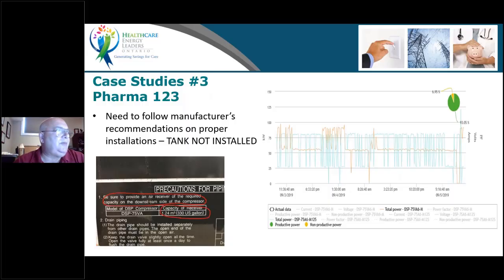This is the exact same customer. What I pointed out to the customer, after 10 years of him having the system in place, is that the name tag on the compressor itself specifically says, be sure to provide an air receiver of the required capacity downstream of the compressor. There was none. These compressors fed directly into the dryers, which affected how these compressors operated.